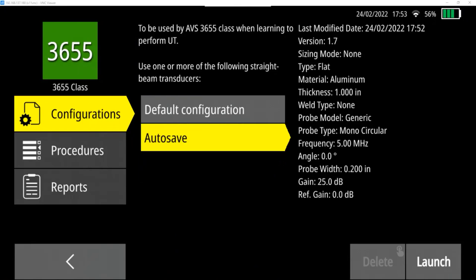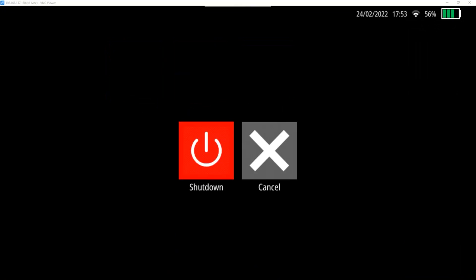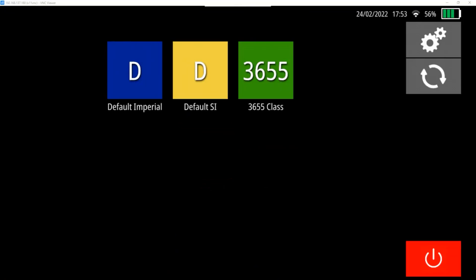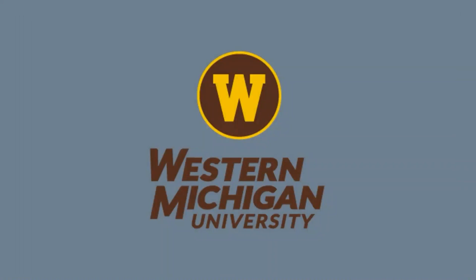When I'm done in this area, I can hit the back button in the lower left. It takes me back to the main screen. And if I'm done with the tester, when we turn it on, there's a physical power button on the tester. For shutting down, Sonatest has – in the manual for this unit, it tells you to use the red button in the lower right corner. So for shutdown, I'll press the button in the lower right. If that was a mistake, I can hit cancel. Or if I am actually ready to shut down, I can press the shutdown button and we'll lose our screen view as the unit shuts off.